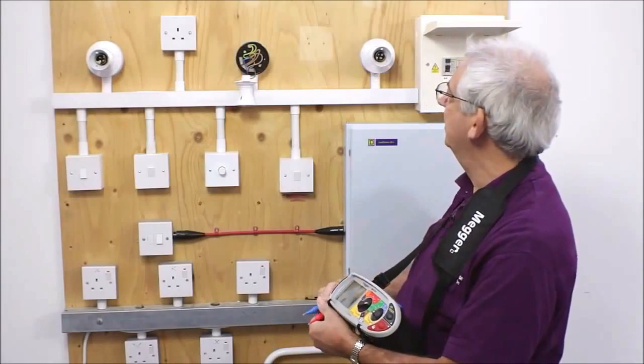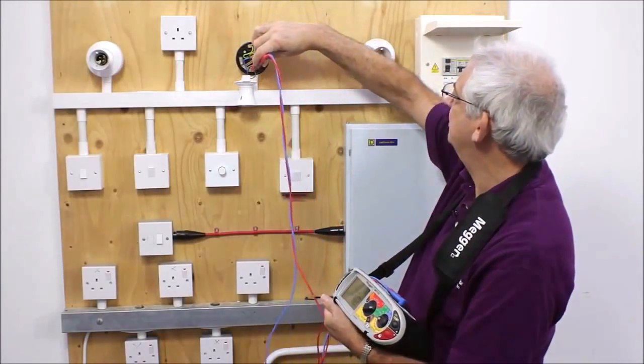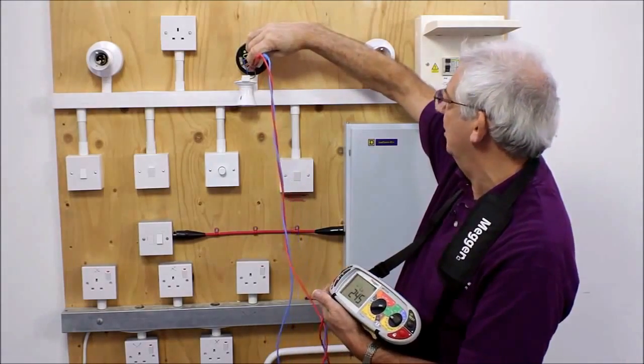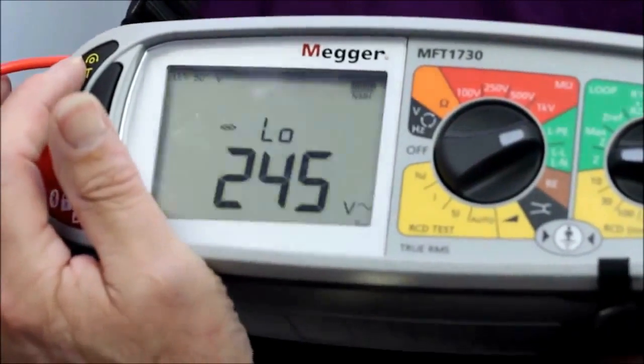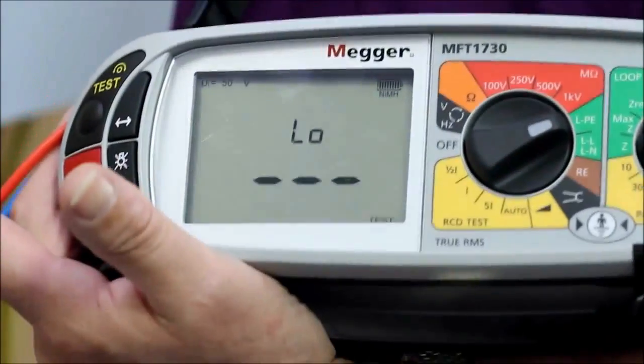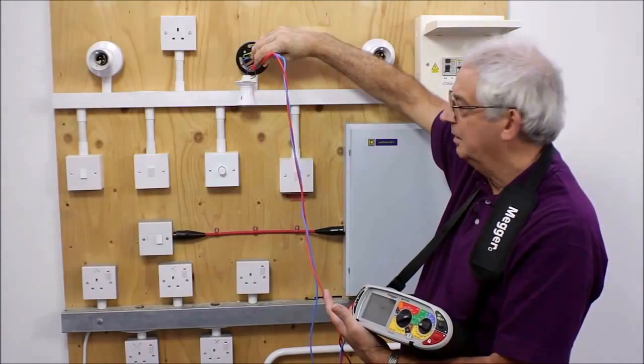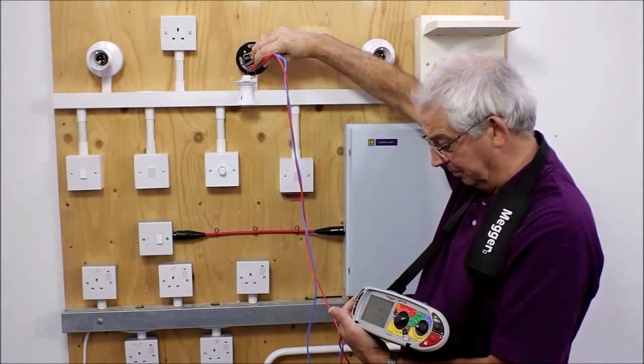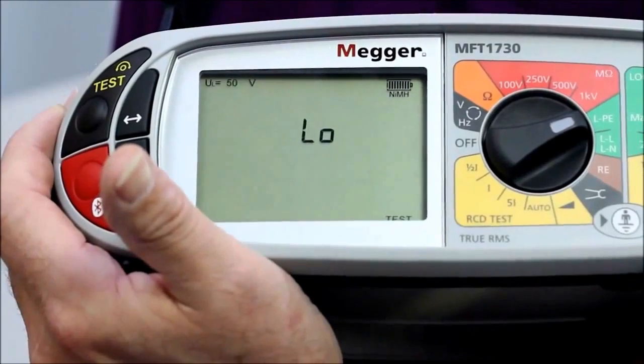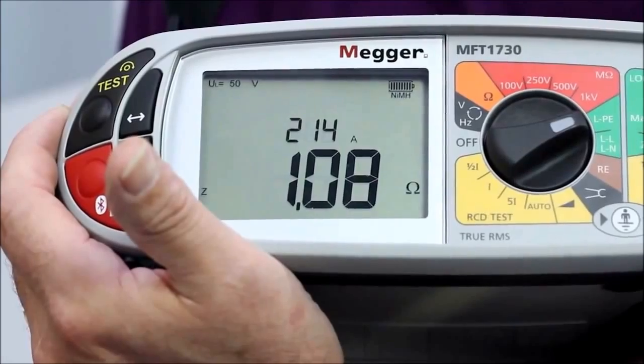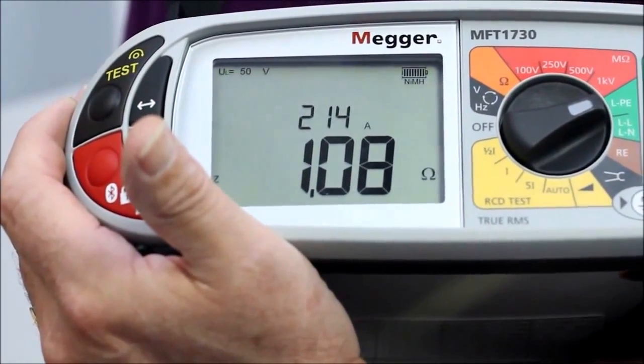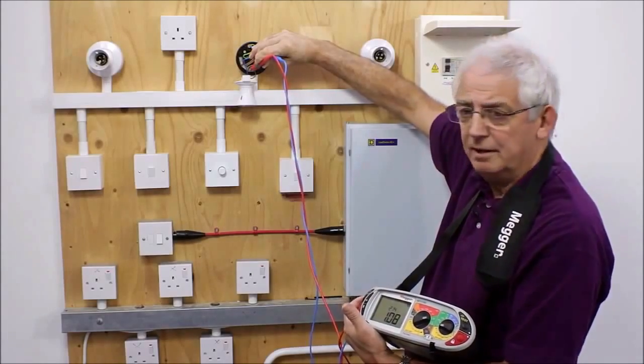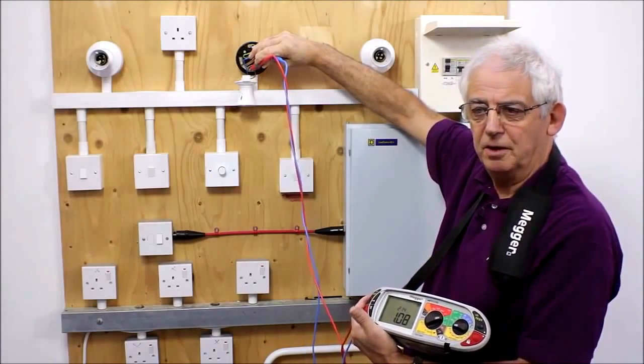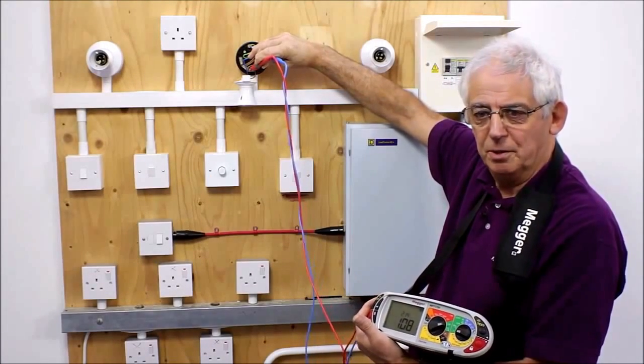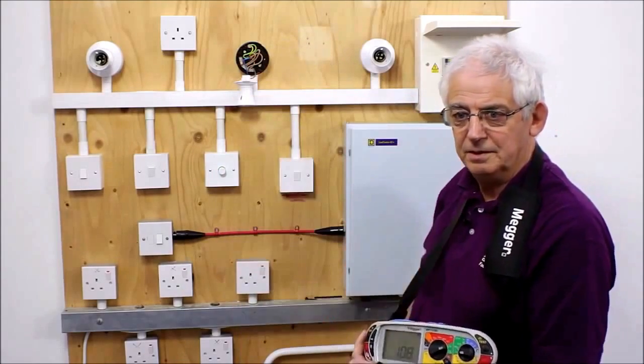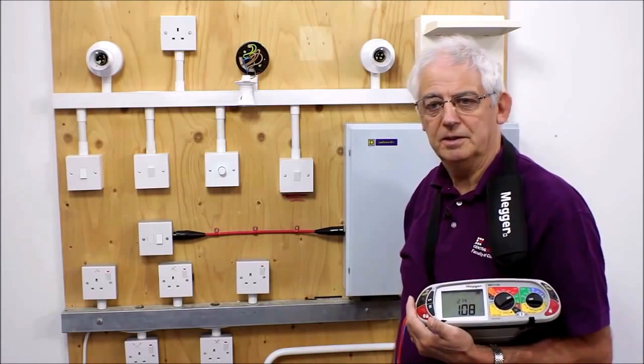Okay, what I need to do now is place my probes, one on the earth and one on the switch return, and push the test button. Because it's pulsing at a very low current, it's going to take a little bit of time, not too long. It always seems a long time when you're waiting, but literally just a few seconds. And I've got a value of 1.08 ohms. That value is perfectly acceptable because it's far lower than the 6.18, which is my maximum. And that's a Zs test on a lighting circuit.